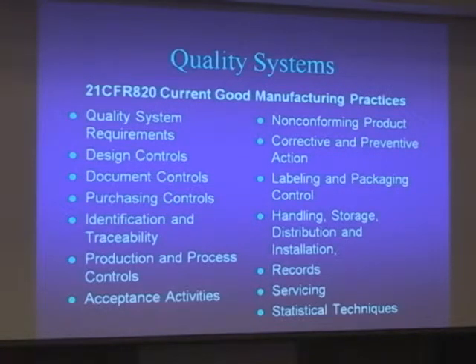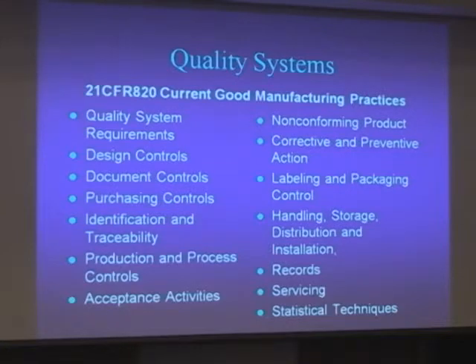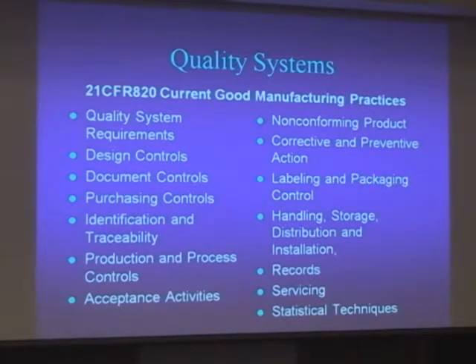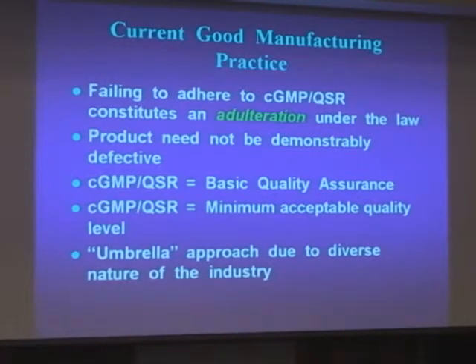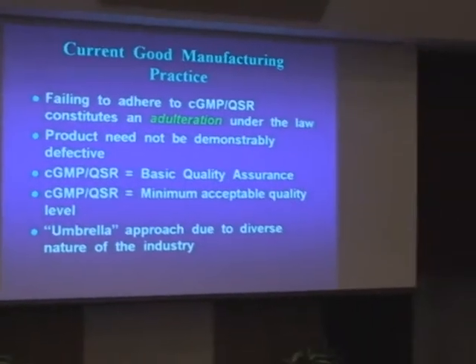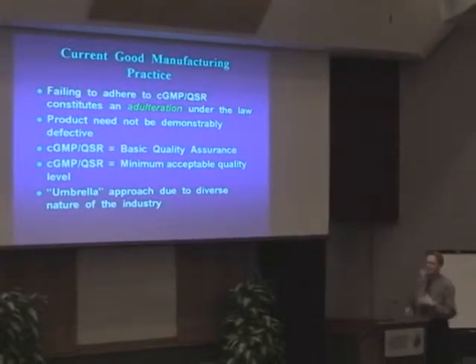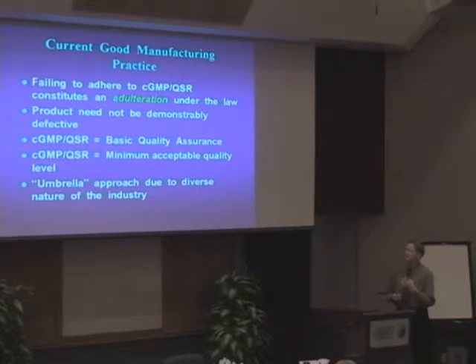Keep in mind that the medical device regulations are a broad umbrella — written for many different types of applications and devices. Some things may not apply to your device; for example, we don't have installation in our medical device. But you do need to find the best way that works with your company and your setup. If you don't follow the GMPs, that's considered adulteration — it's not just having a foreign matter in your product. Simply not following the GMPs is adulteration. GMPs are the minimum requirements.